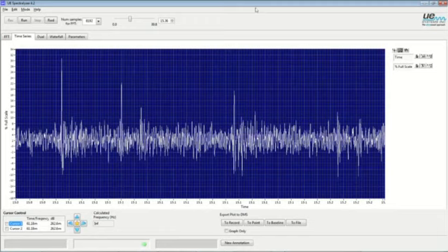There we go. That provides a real good view. So between this discharge and this discharge, we see the distance in between there is strikingly different between these two and these two, and these two. That is a signature of a tracking event taking place on an insulator.